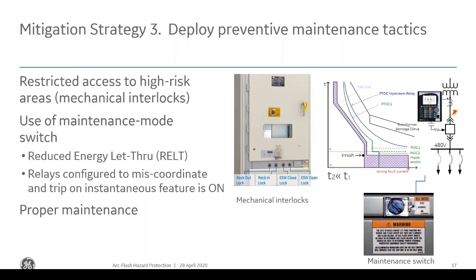But it's very easy to maintain. Most electronic microprocessor relays on the market make this very easy to do. You can add a maintenance switch or a push button of some sort. You can see one mounted on this panel over here. You could use a push button on the relay, or if you have communications to the relay, you could do it from SCADA, so you could put it in maintenance mode before you even go out there to do work. The effect is that you're bypassing all of these coordination curves and tripping very close to the arc flash incident, where you're going to reduce that time significantly.